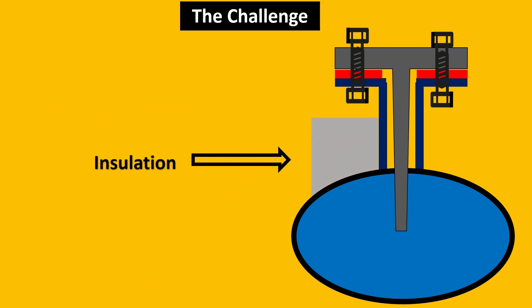The challenge is when you have insulated lines. So when you put insulation here the clearance space will reduce drastically. So you might have to sometimes even cut through the insulation to actually remove the thermowell. This is very hazardous and nobody would want to waste their insulation. So in this case what are the possible solutions? Let us look into that case.